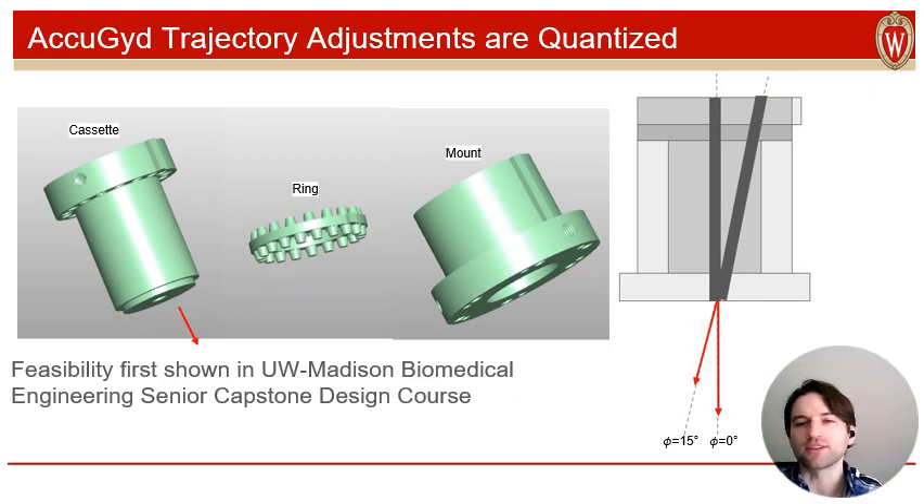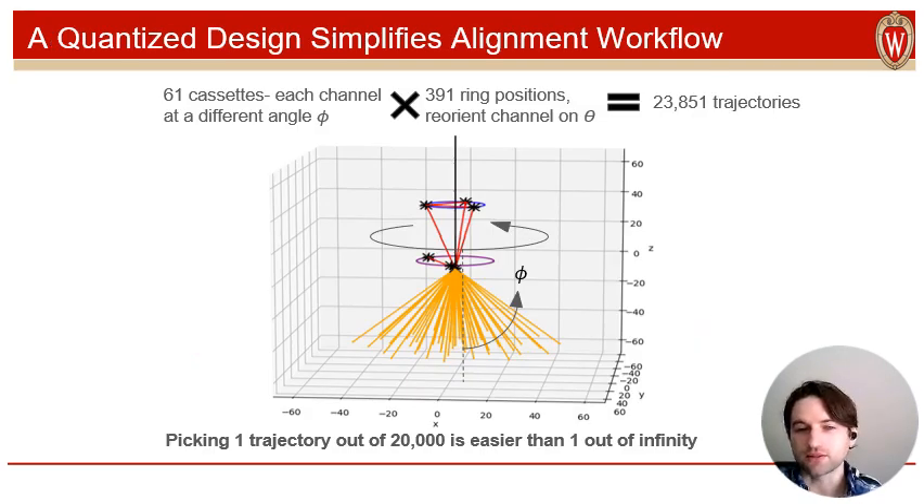While prior methodologies employed continuous gears for alignment, the AccuGyd has a quantized configuration. Its three pieces slot together — the mount, the ring, and the cassette — and can all be rotated relative to each other, thanks to this array of teeth around the ring. We actually have a set of 61 different cassettes, each with its channel at a slightly different angle relative to the central axis of the device. As you can see here, switching out the cassette can change the alignment of the central channel by up to 15 degrees off-axis. Between ring rotation, which we could call variable theta, and cassette choice, variable phi, there are 23,851 unique trajectories that users can define with the AccuGyd.